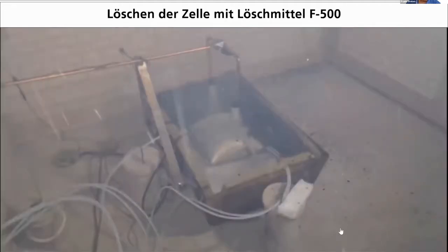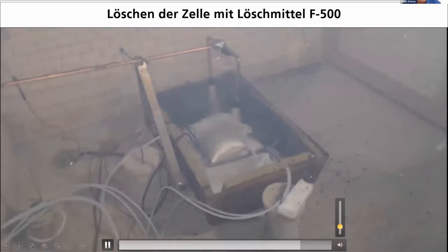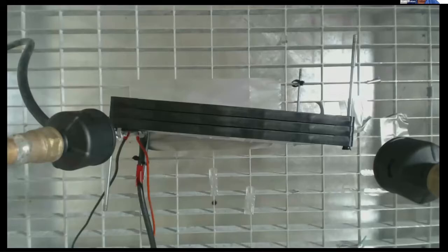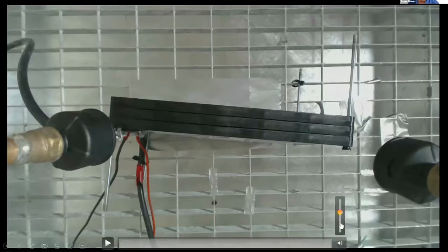Another application, seeing the agent actually on the outside of that pouch style battery, but it was still able to cool it and drop it below the ignition temperature for thermal runaway. If you watch this one, this is another pouch type battery. Look at the two nozzles and where they're directed - you'll see they can't get right inside the pouch, but they're more around the battery itself.